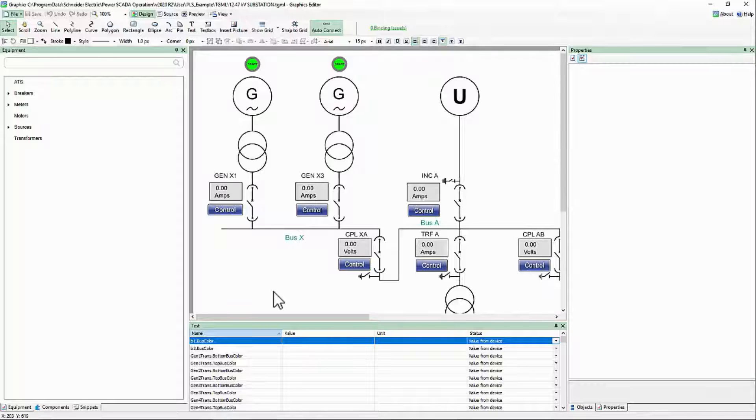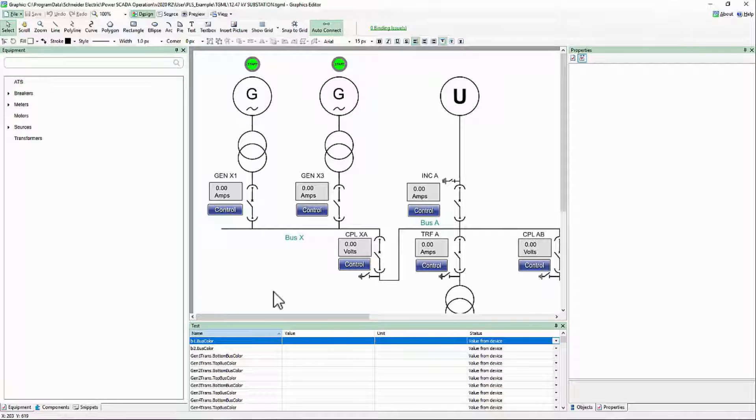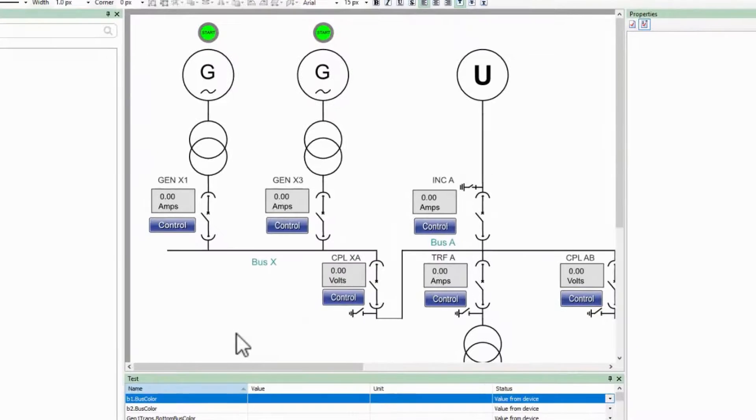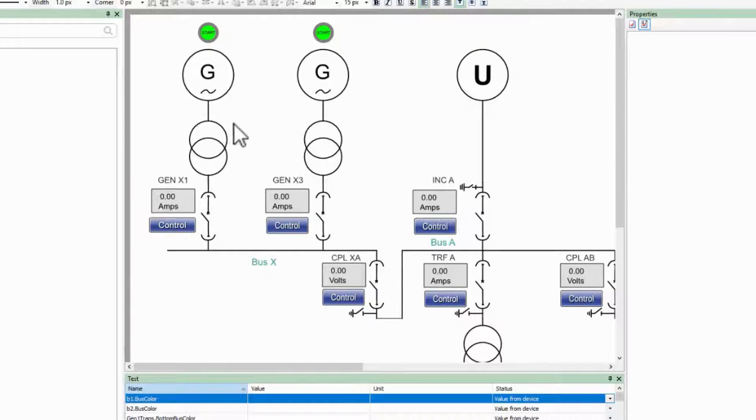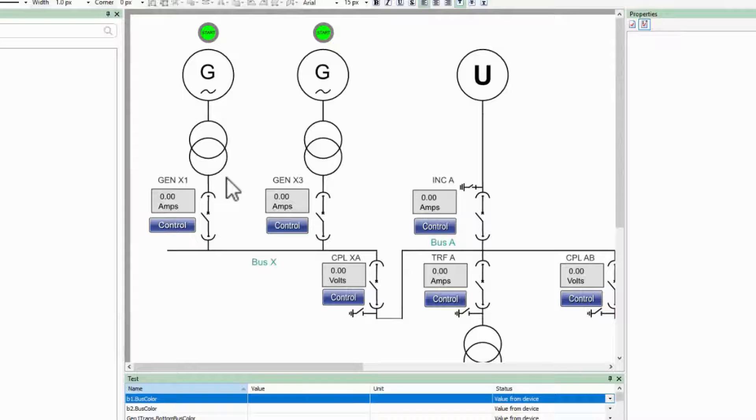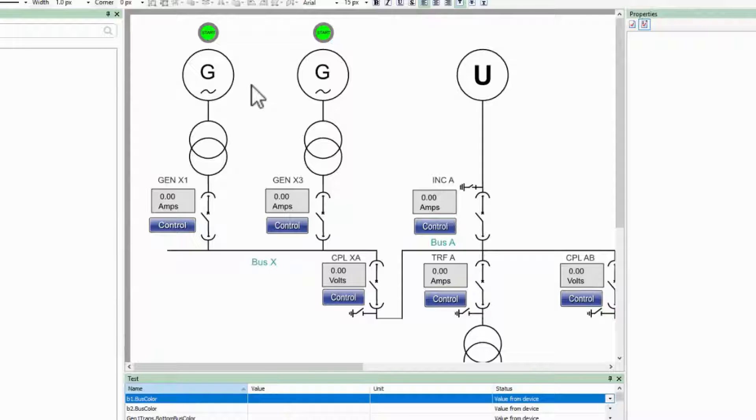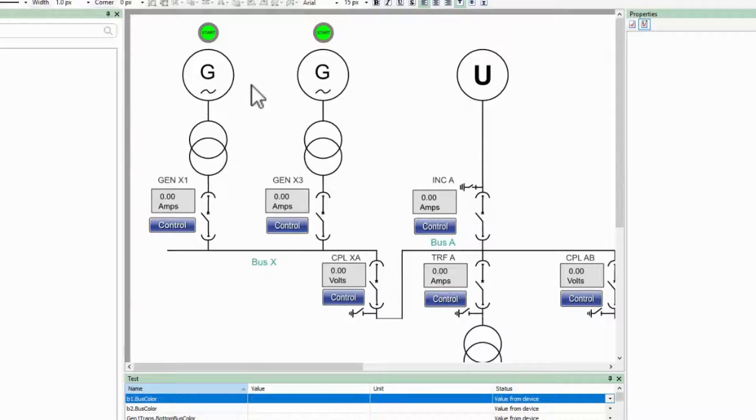Alongside the graphics, we also have an engine running called Advanced One-Line, which allows us to change one-line bus colors based on their energized status, the sources feeding them, and indicate if they are being fed by parallel sources. This allows an operator to quickly determine the state of their network.